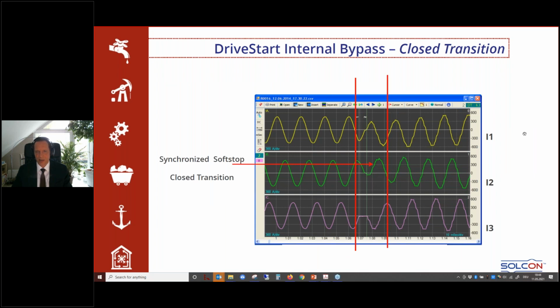Here you can see it with a little bit higher resolution. There you have the synchronized soft stop. In this case, we are transferring back to the inverter. Here you have normal network supply. Here you have the inverter supply, and there is really no spike or no bump, and it's really a very smooth transition.